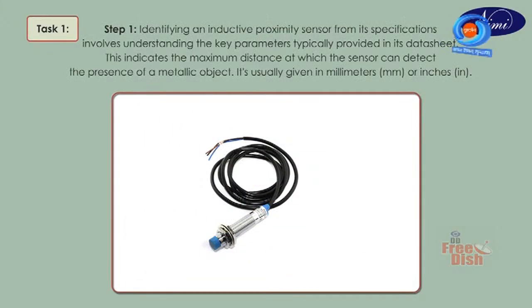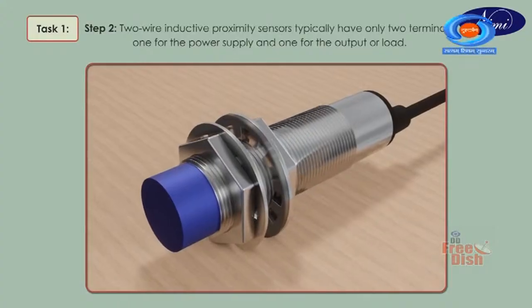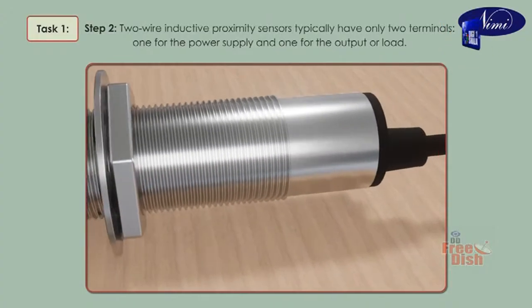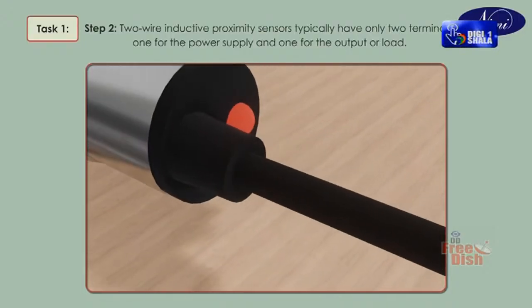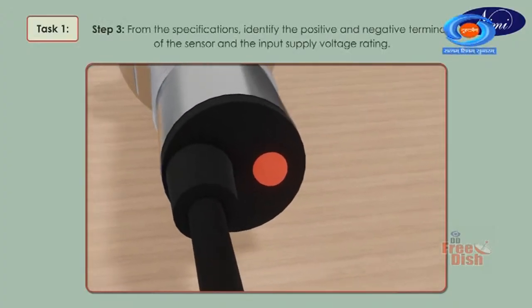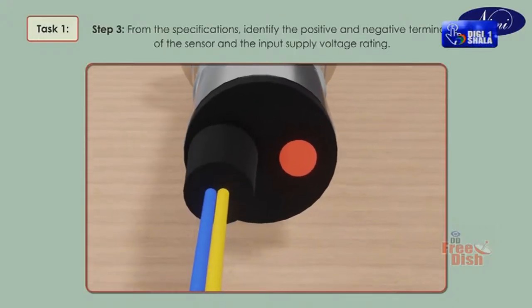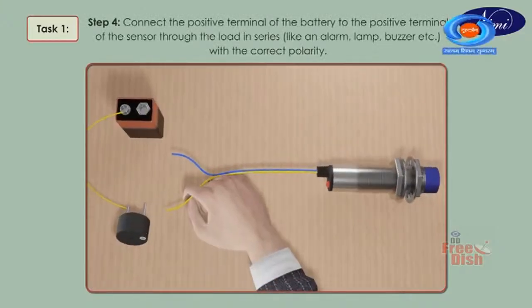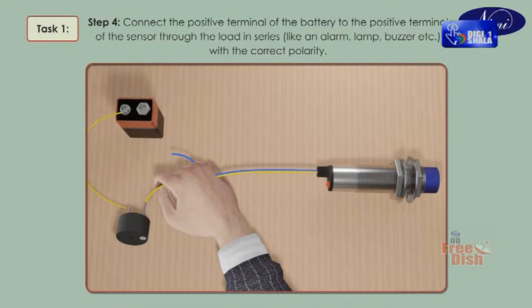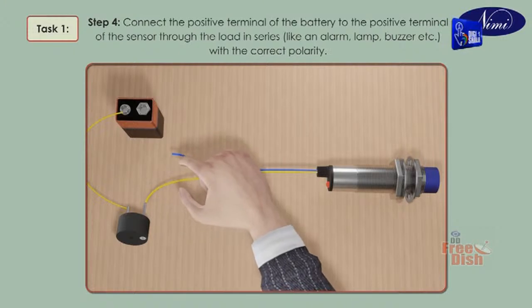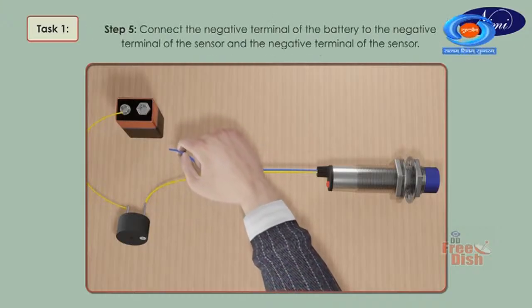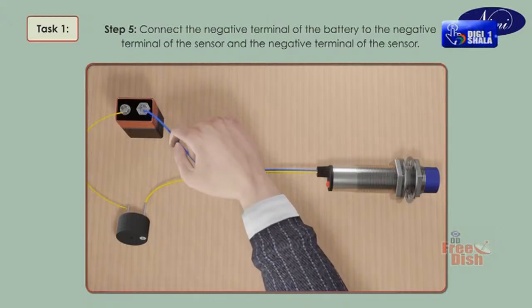Task 1. Detect different objects using inductive proximity sensors. Step 1. Identifying an inductive proximity sensor from its specifications involves understanding the key parameters typically provided in the datasheet. This indicates the maximum distance at which the sensor can detect the presence of a metallic object. It's usually given in millimeters or inches. Step 2. Two-wire inductive proximity sensors typically have only 2 terminals, one for the power supply and one for the output or load. Step 3. From the specifications, identify the positive and negative terminals of the sensor and the input supply voltage rating. Step 4. Connect the positive terminal of the battery to the positive terminal of the sensor through the load in series, like an alarm, lamp, buzzer, etc., with the correct polarity. Step 5. Connect the negative terminal of the battery to the negative terminal of the sensor.